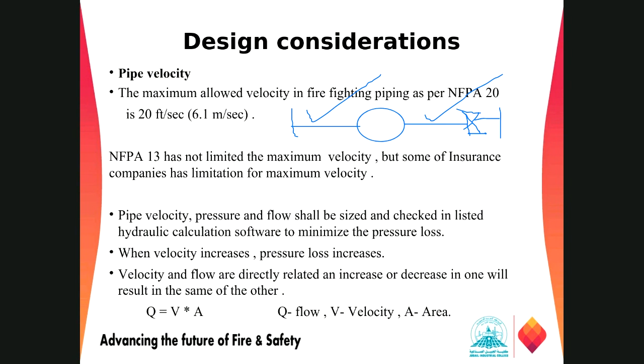But NFPA 13 doesn't limit the maximum velocity in the sprinkler system, though some insurance companies have given a limitation. The problem is that if you have high velocity in your piping, we need high pressure to discharge water into the sprinkler, because the higher the velocity, the higher the friction with the wall of the pipe. So there will be high frictional resistance.